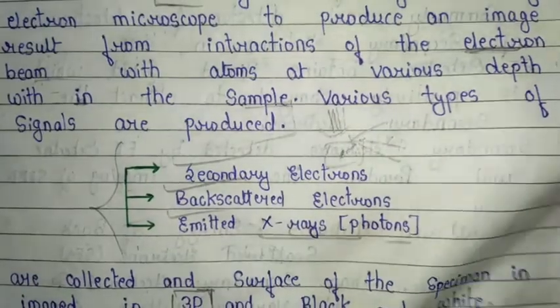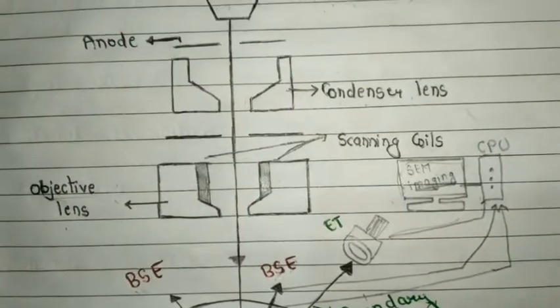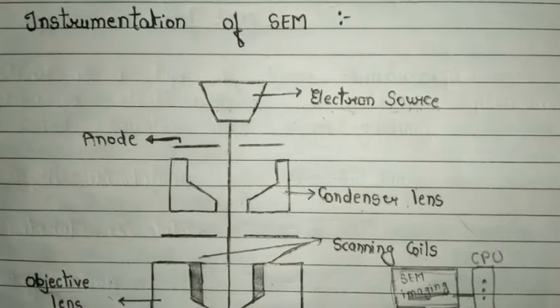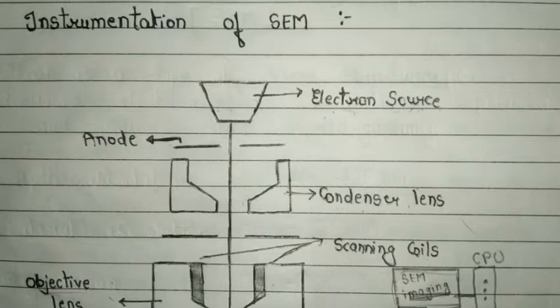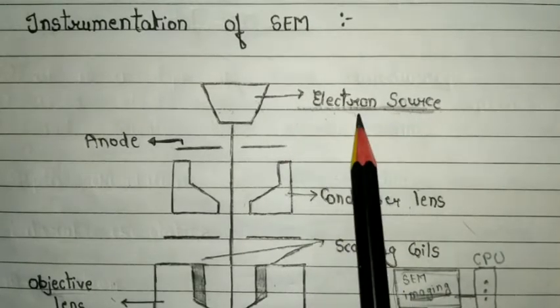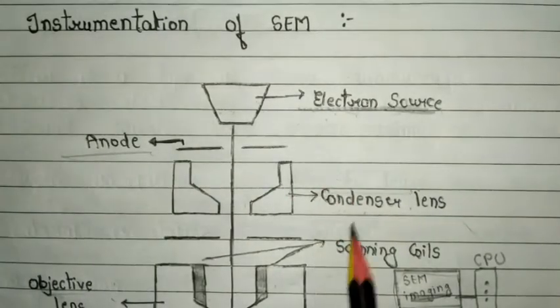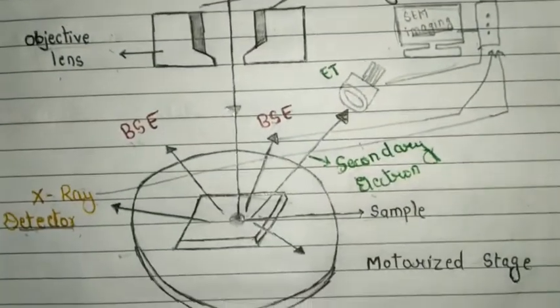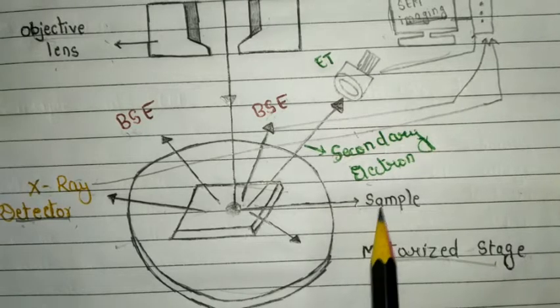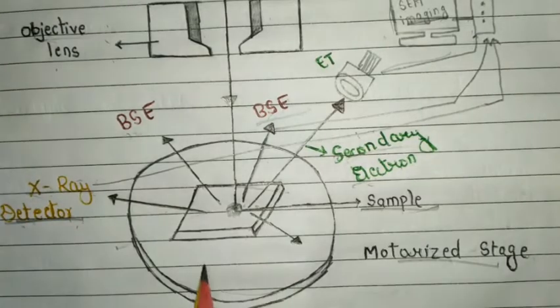The instrumentation part of the scanning electron microscope is very important. When we discuss the instrumentation of SEM, we need to know about every single part. The parts include: electron source, electron beam, anode, condenser lens, objective lens, scanning coil, and a motorized stage in which we place the sample specimen. There are also secondary electron, backscatter electron, and X-ray detectors. All these signals are obtained after the electron beam is bombarded onto the sample.